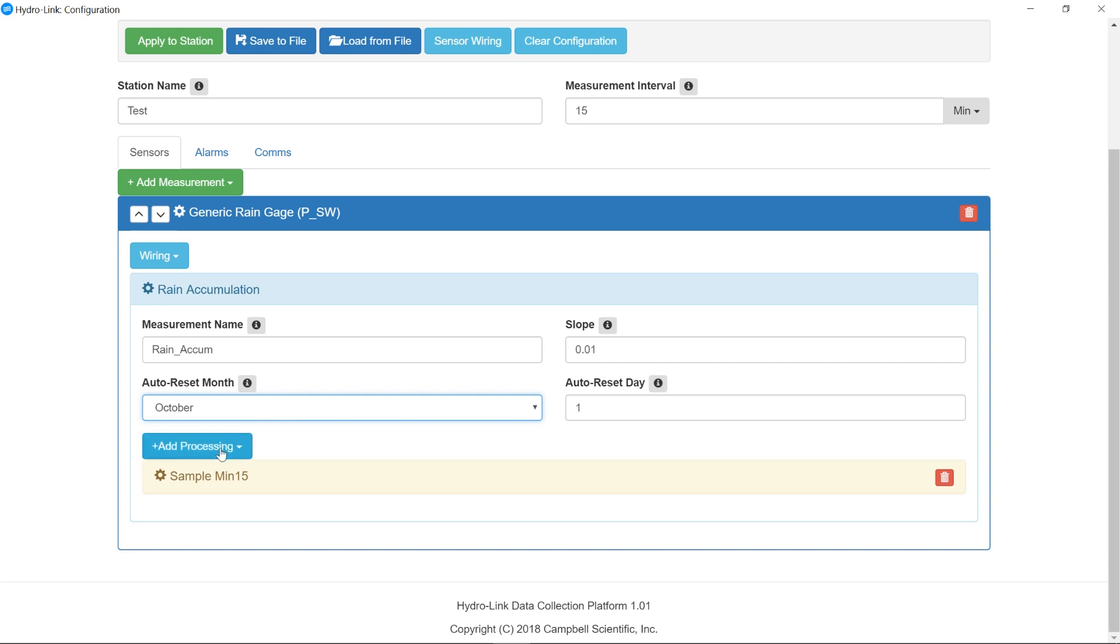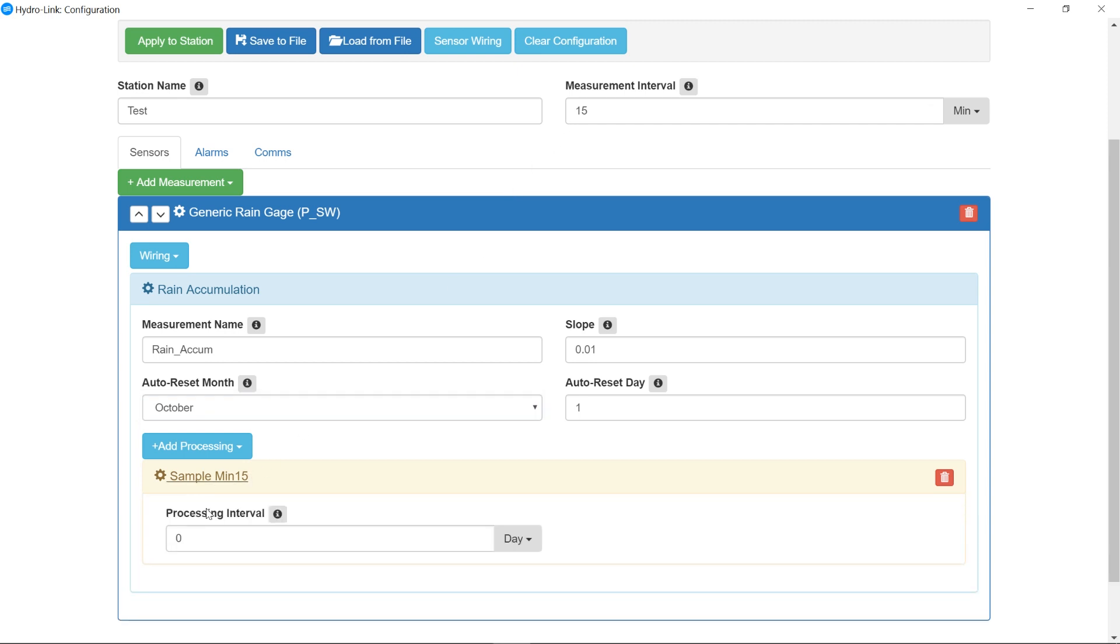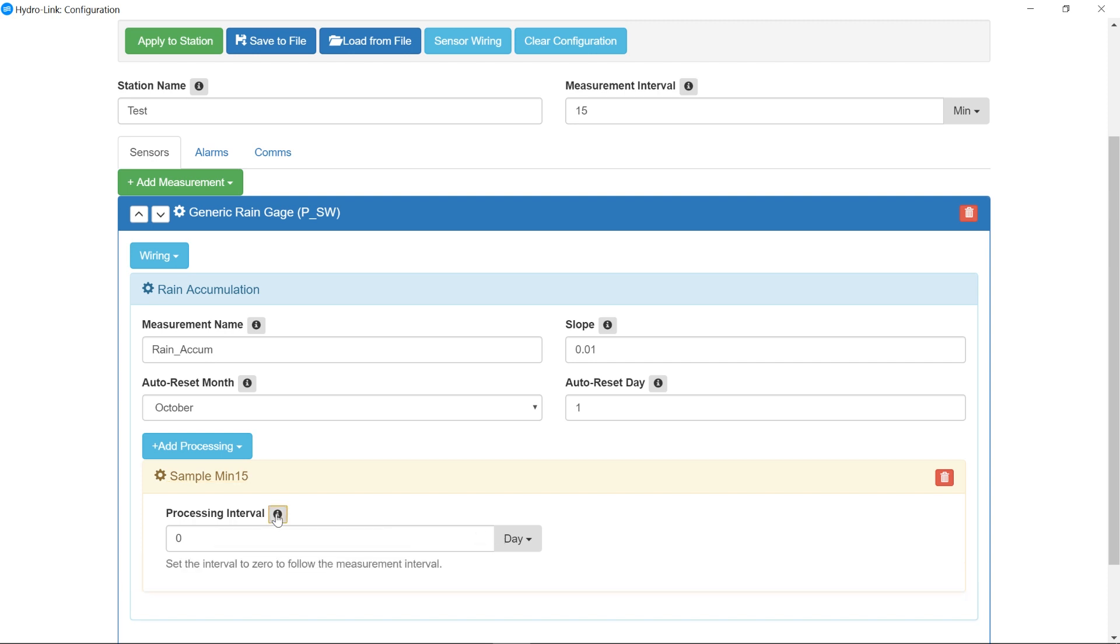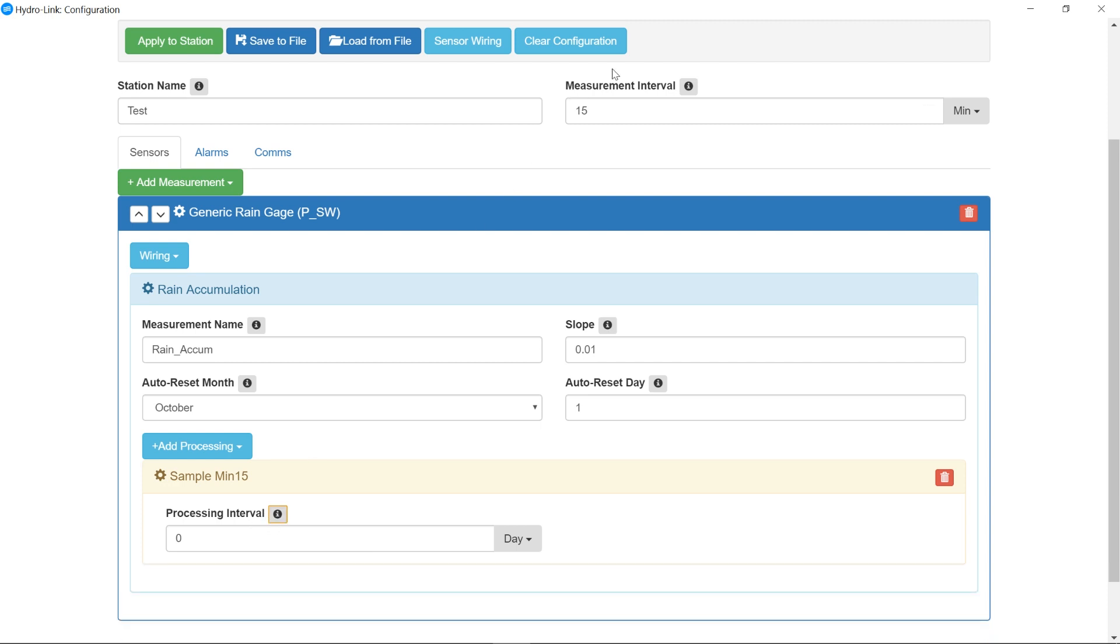Your processing is how the data is actually going to be stored. So in this case here, sample min 15 is minutes 15, and that's going to follow this rate right up here. If I expand this, it says my processing interval is zero days. And if I look at this note here, it says if this is set to zero, then it will follow the measurement interval. So the default is zero because in most cases, you're just going to be following this rate up here.